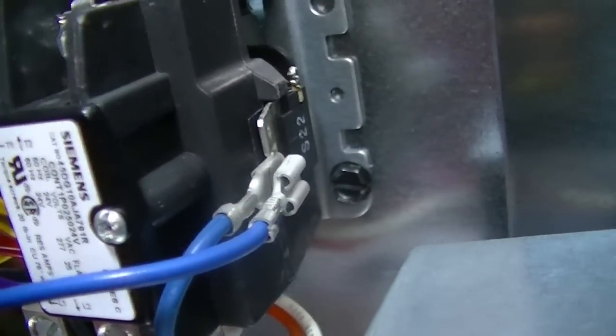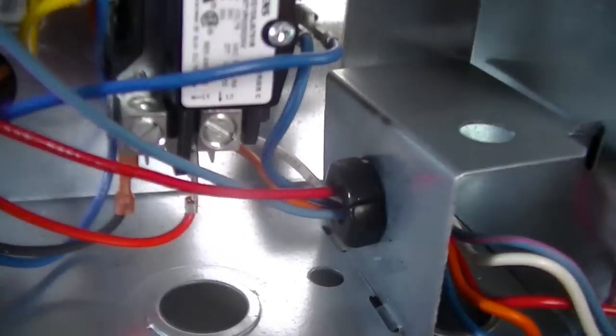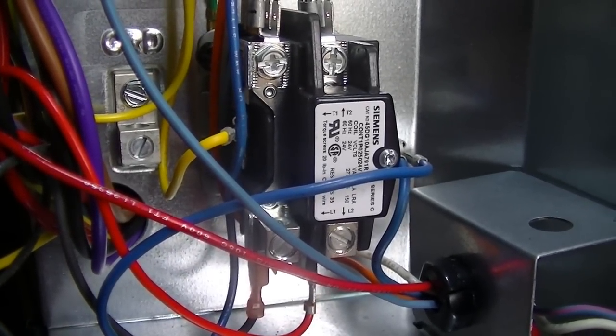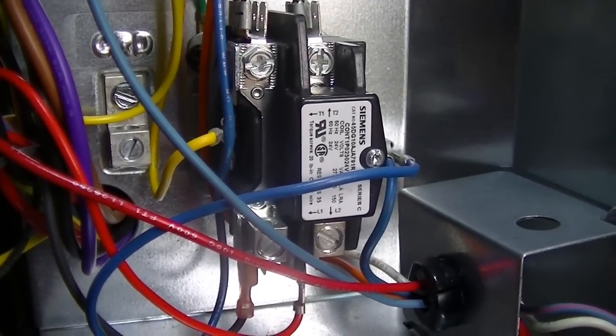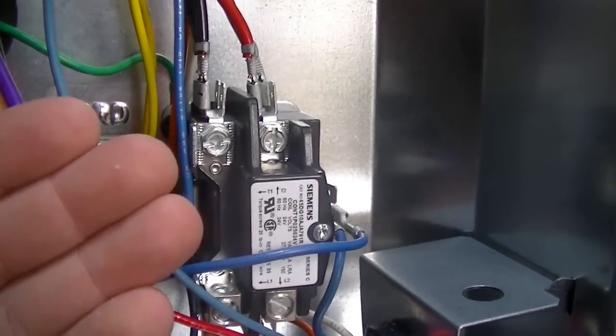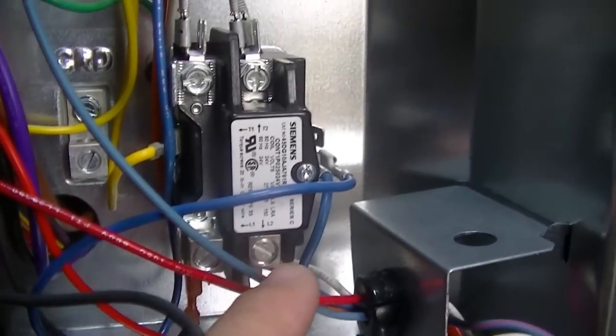There's a low voltage coil on the back side which you can see a little bit right through there. See if we can get a light on. The low voltage coil on the back side, you see the copper color there. When low voltage passes through that coil, it creates magnetism. Switch closes underneath here. Magnet pulls it down. Voltage flows through here.